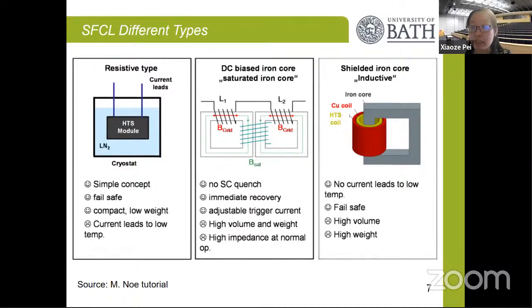So when you put it into the grid during normal operation, it is basically invisible. Then when a very high fault current happens, this high fault current drives the superconducting tape from the superconducting state through its transition period and then to the normal conductor state. So it changes into a resistance in the power grid to limit the fault current. This is a very simple concept and a very compact structure. I'm going to show you some demonstration projects using this type.